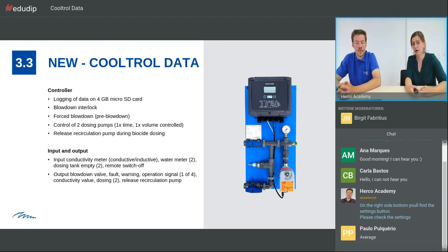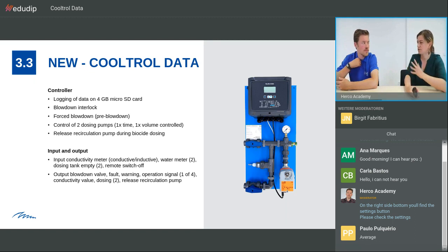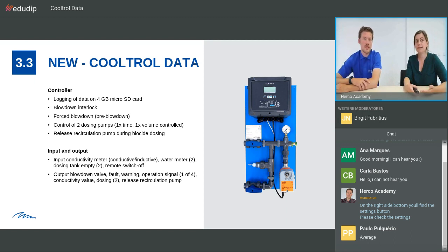So we have the blowdown interlock, to avoid any loss of biocide directly to the wastewater. We have the forced blowdown or pre-blowdown, and we control two dosing pumps. A difference to the previous controller is that with Cooltrol, you could set the dosing pumps like you want. So let's say 2 times time control, or 2 times volume control, which is nice because of the flexibility, but also problematic if the operator, let's say, confuses the two dosings. Yes, of course. So in this case, we have a fixed setting. One dosing is definitely time controlled, biocide 1, and the other one is definitely volume controlled, the corrosion inhibitor.